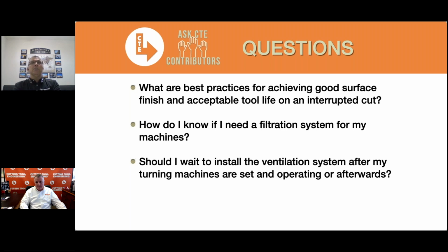Again, speaking from experience, most staff at the facility will get the machine set, and the filtration is usually an afterthought. But most manufacturers have enough data available to allow someone like myself to design that ventilation system up front. It really revolves around three components. The first one is the size of the machine, the volume of the cavity when the doors are closed and the machine is doing its thing.